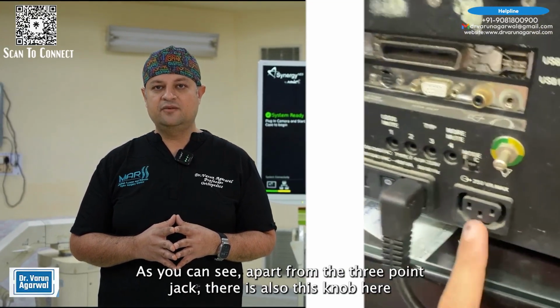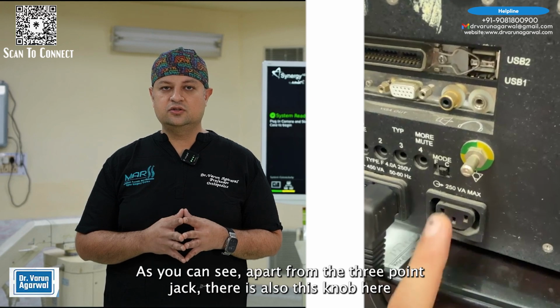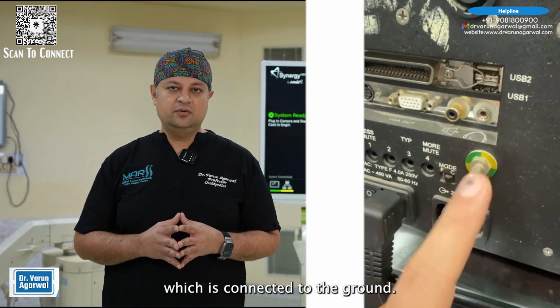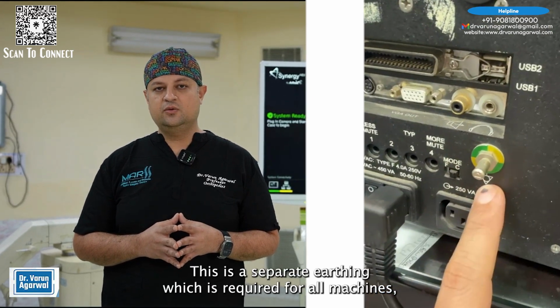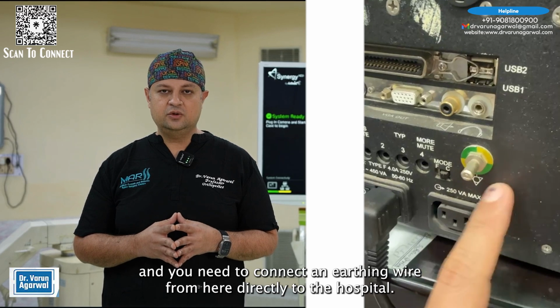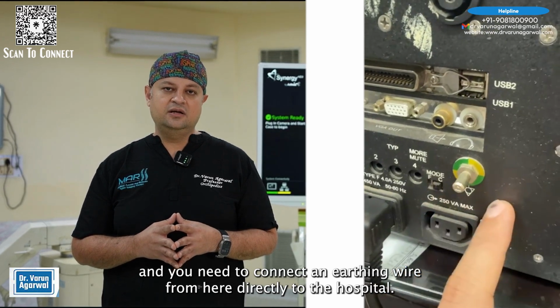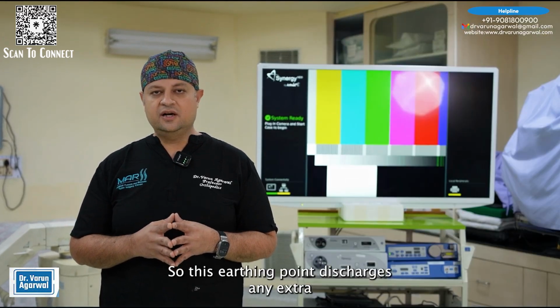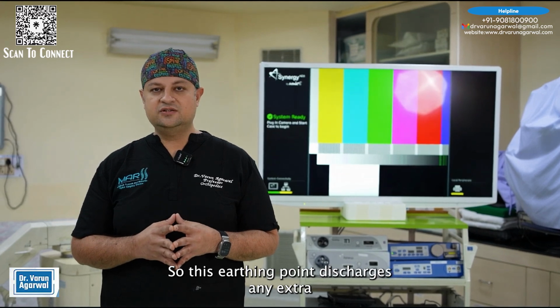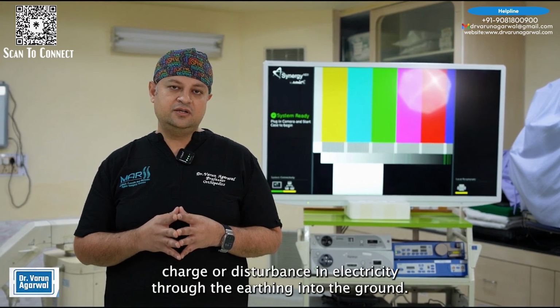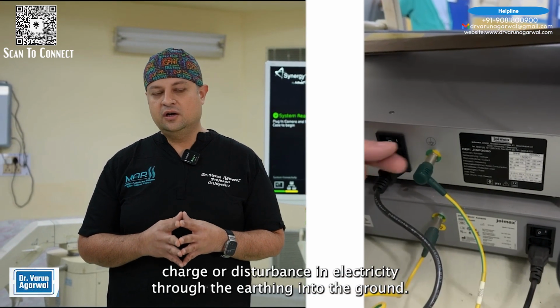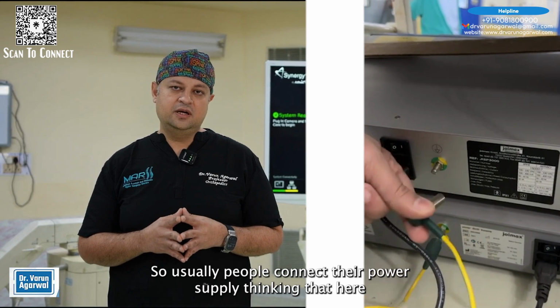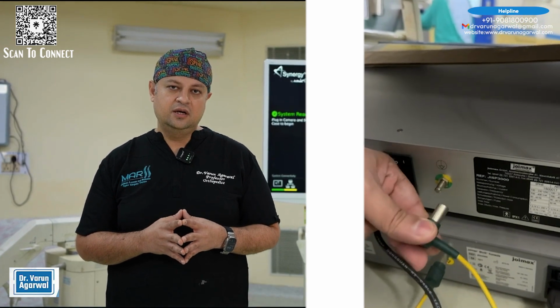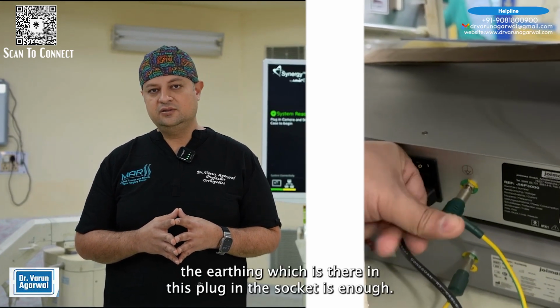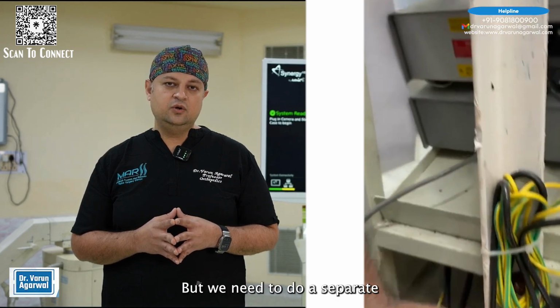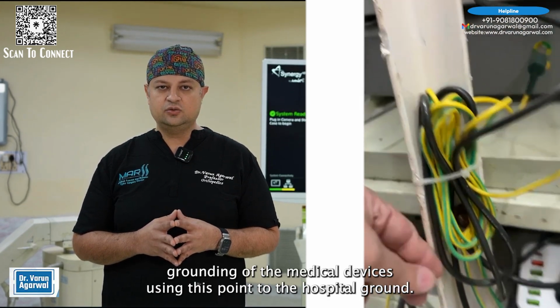One important thing is earthing the machine. As you can see, apart from the 3-point jack, there is also this knob here which is connected to the ground. This is a separate earthing which is required for all machines, and you need to connect an earthing wire from here directly to the hospital ground earthing. So this earthing point discharges any extra charge or disturbance in electricity through the earthing into the ground.